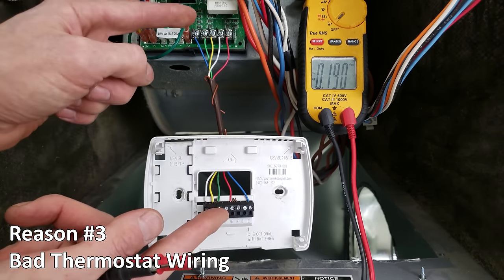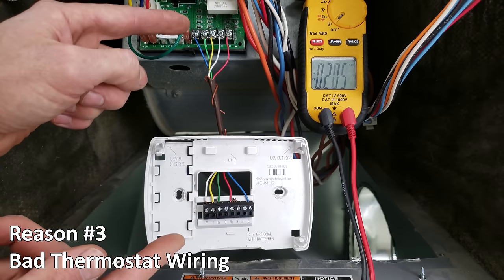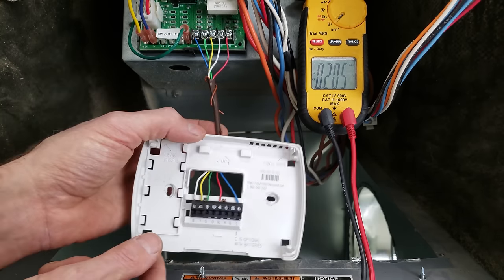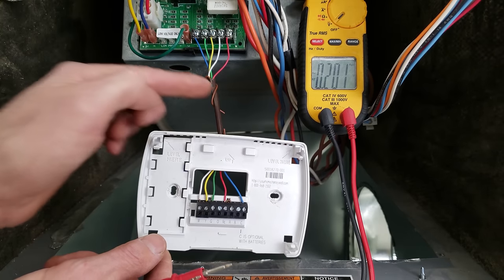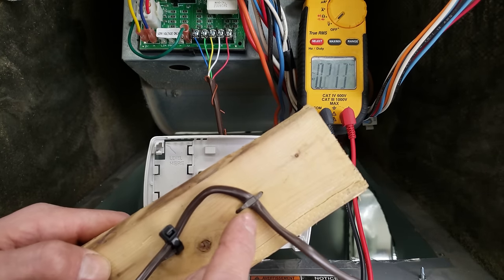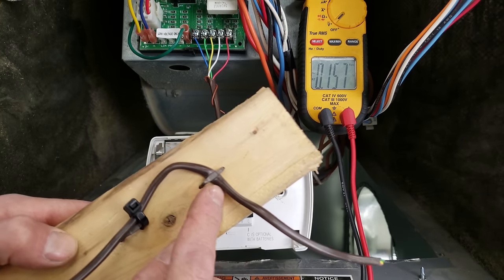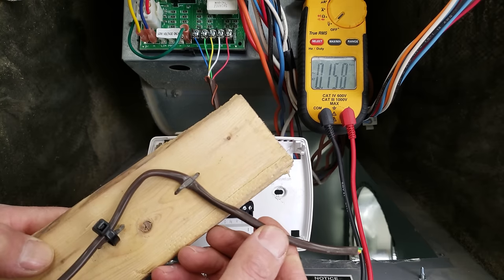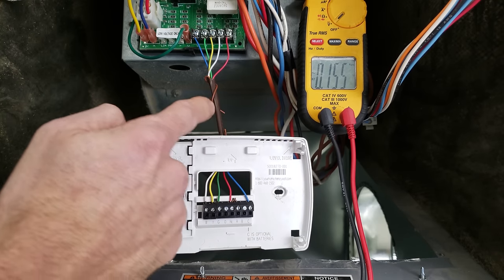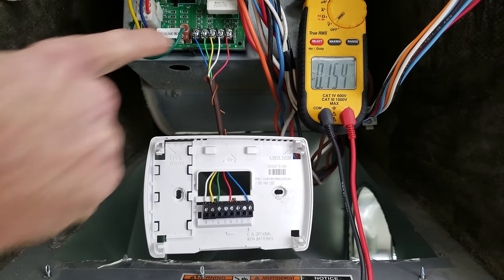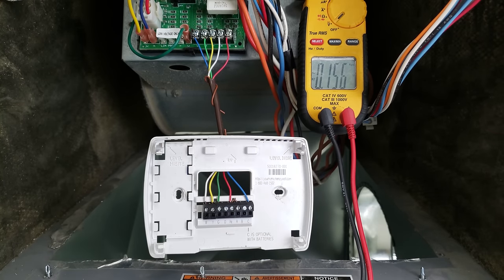Problem number three is when the thermostat wire is the problem. So in this case, you see, I just have a short section of wire right here from the control board to the thermostat, just to show you, but this would typically be running through the building. But if somewhere in the building the thermostat wire was squished by a staple or maybe chewed by a mouse or something like that, it could be accidentally connecting the R and G wires. So what I'll do is measure with my multimeter to see if we do have power from G to common.